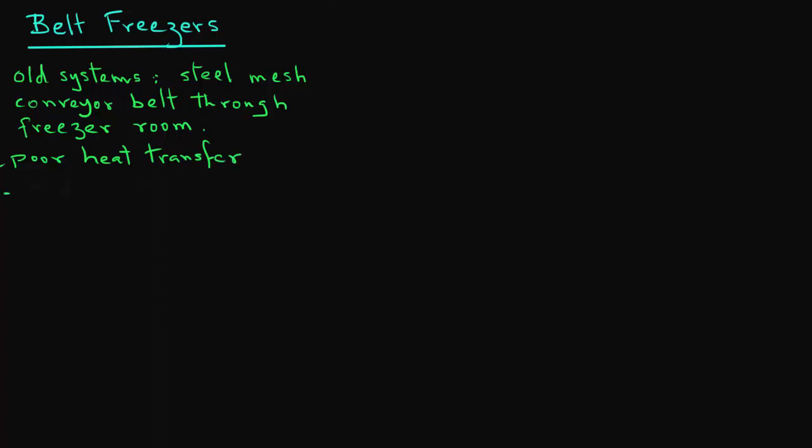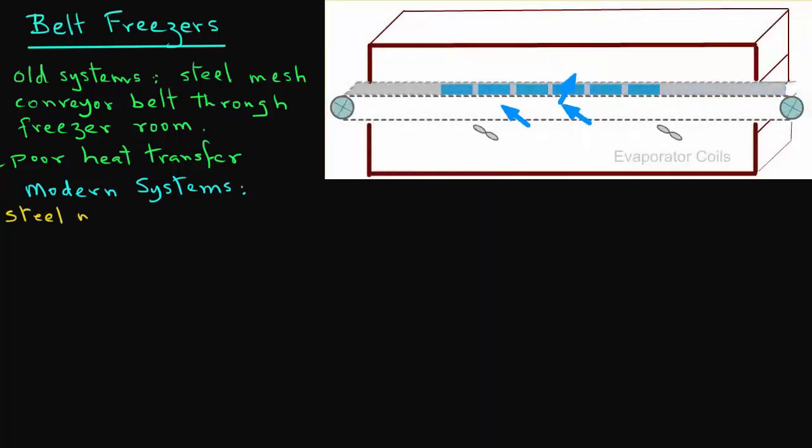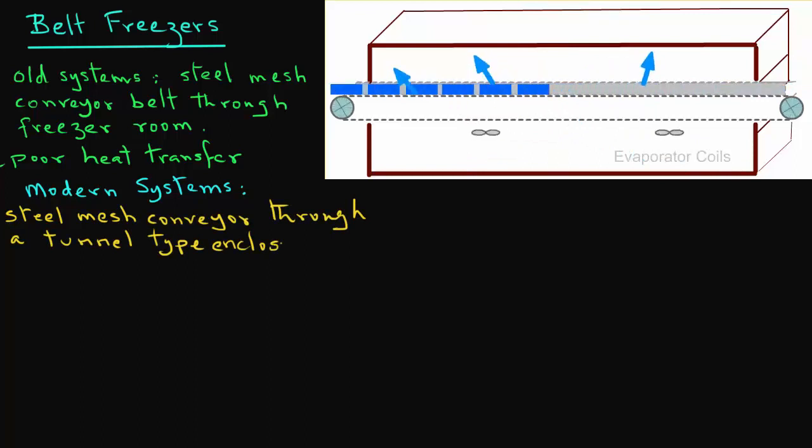In the modern systems, again a steel mesh conveyor is used, except it is run through an insulated tunnel type enclosure. In tunnel type belt freezers, air moves up through the product and there is good contact between air and the product.